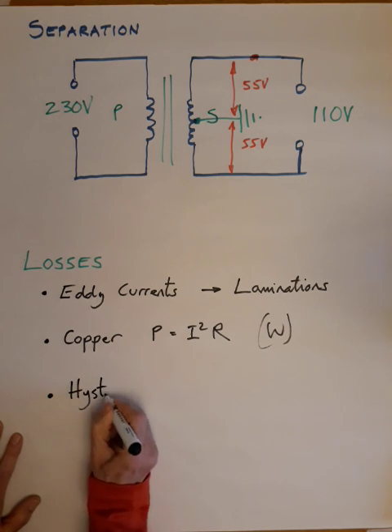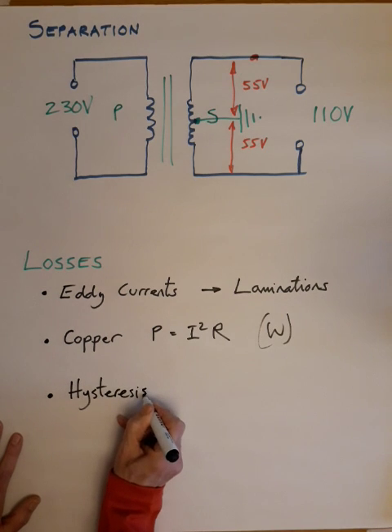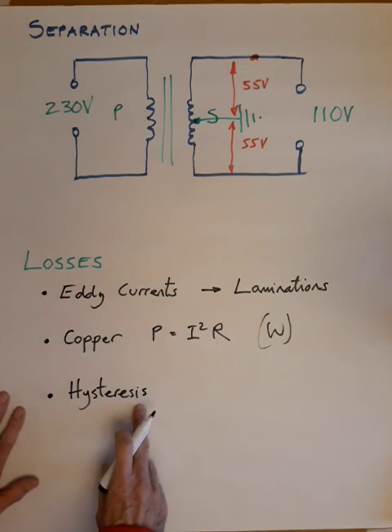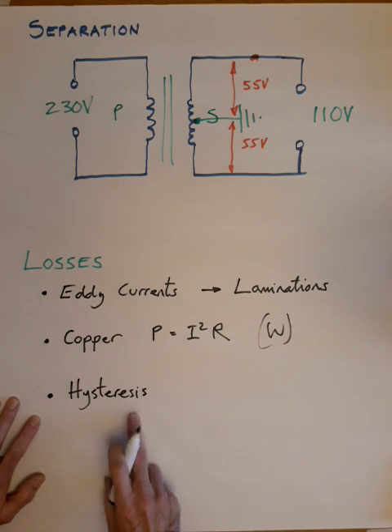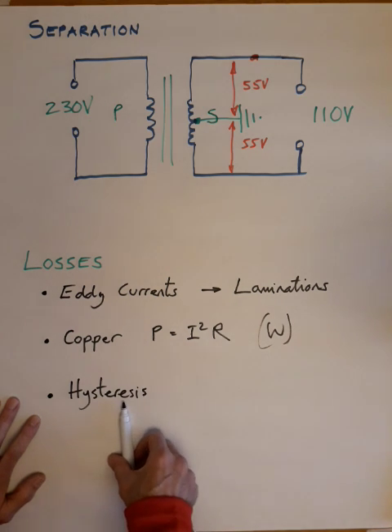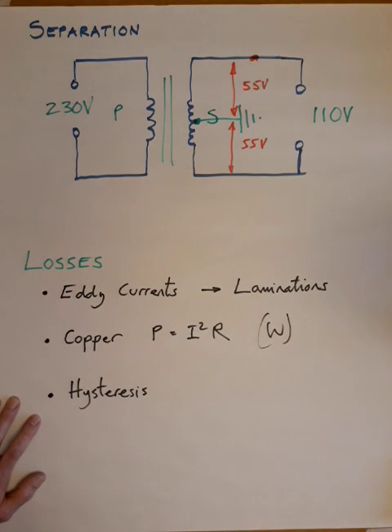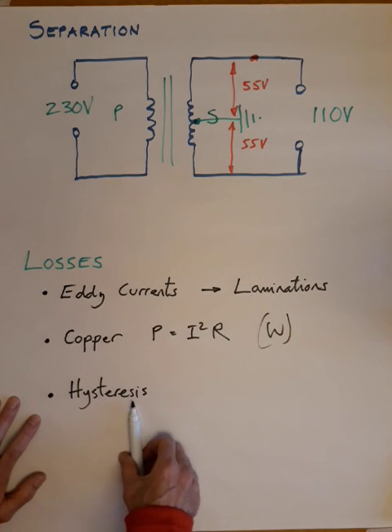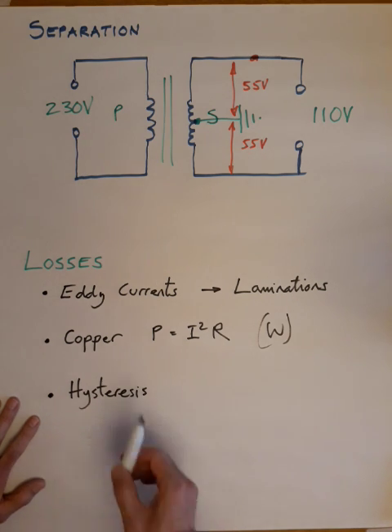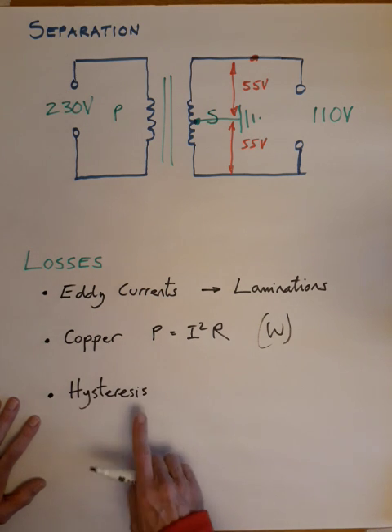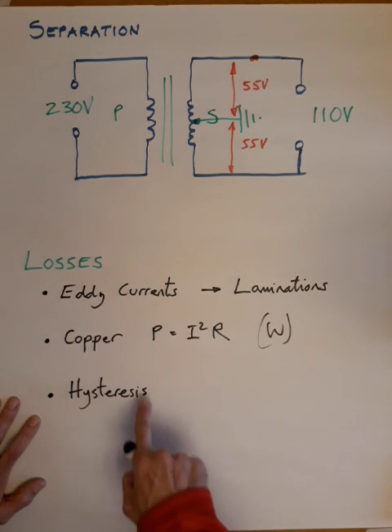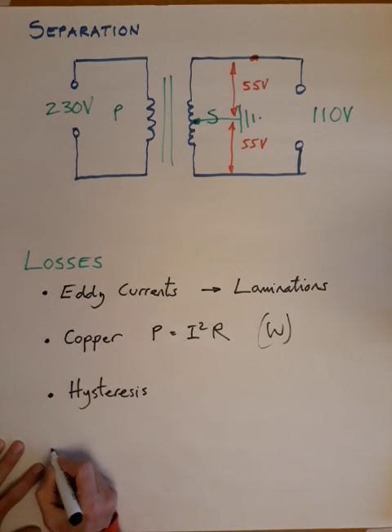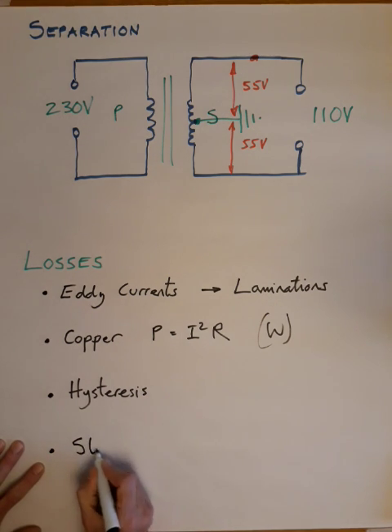The third one is hysteresis. There's a totally separate handout explaining hysteresis in your notes, but hysteresis is the process of magnetizing and demagnetizing a piece of material, and that has to happen to this transformer core every time we connect an AC supply to it. If we're magnetizing and demagnetizing something using an electromagnet, we're wasting energy having to demagnetize it before we can remagnetize it. That's what hysteresis is all about. Refer to the handout. The final one is stray losses.